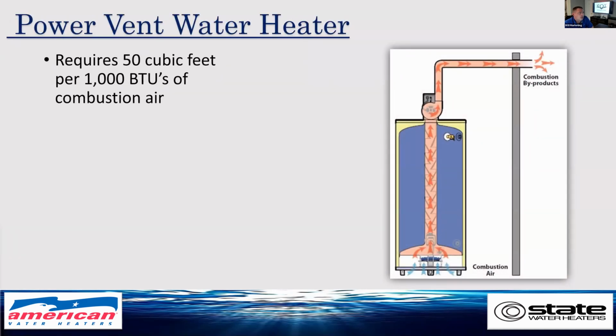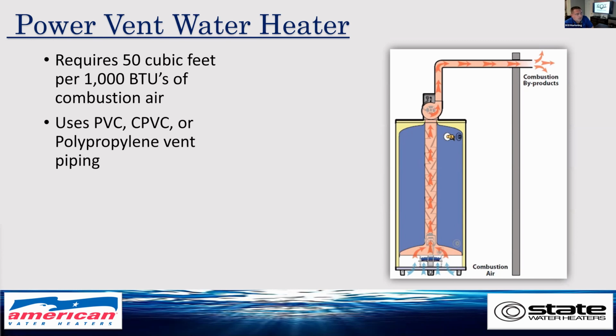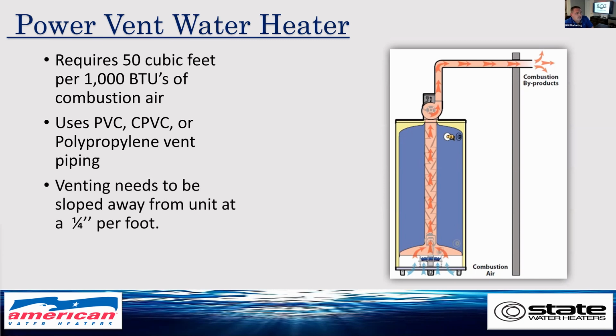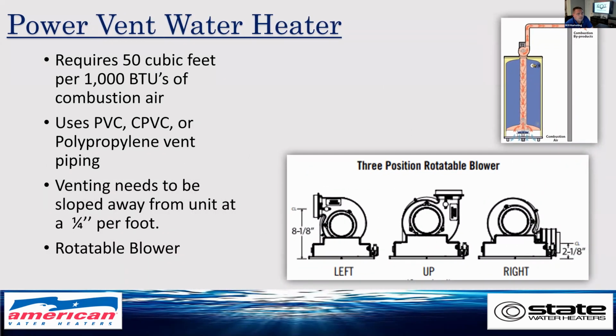A Powervent water heater requires 50 cubic feet per 1,000 BTUs of combustion air. Very important part. It uses PVC, CPVC, or polypropylene venting pipe. The vent needs to be sloped away from the unit at 1/4 inch per foot. It has a rotatable blower. This 3-position rotatable blower comes in handy when you have a restricted head height. It's also important to know, coming off of that, you need 6 inches of pipe before your first turn. So if you look here, right off of here, you need 6 inches of pipe before you put an elbow on.